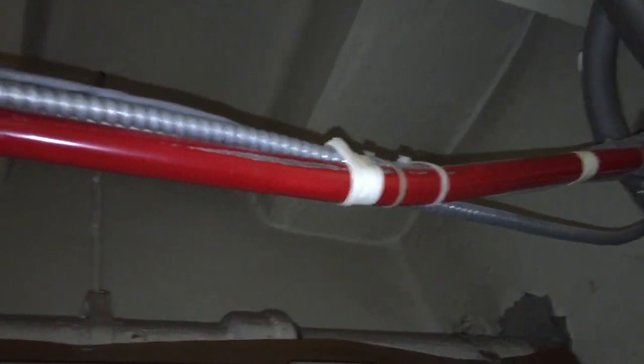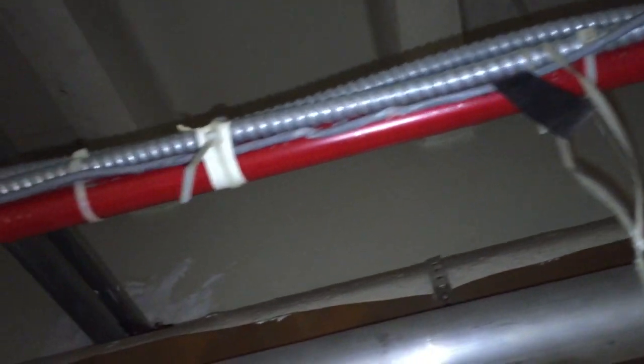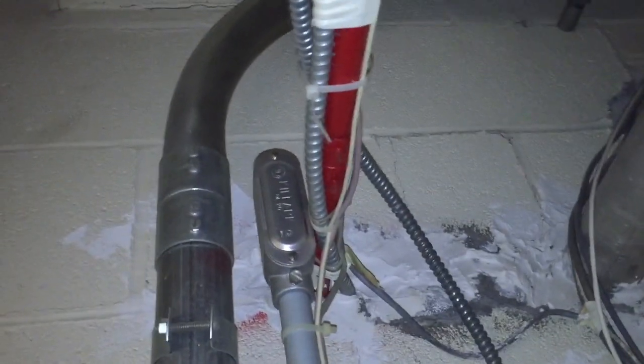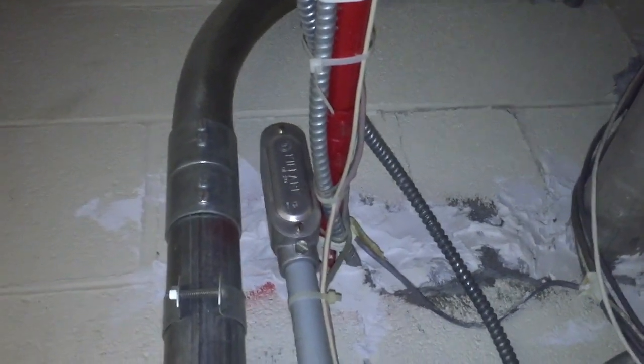Hello and welcome to Moving Violations. This is Russ LeBlanc, NEC Consultant for EC&M Magazine. Check out all these cables secured to this EMT. It's painted red so I'm assuming it's for some fire alarm circuits, but not 100% sure. But in any case, what we have is a violation of section 300.11(c).